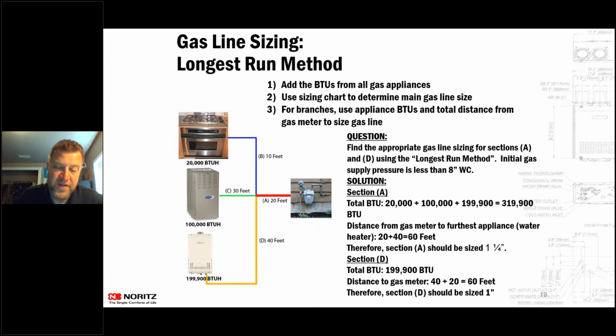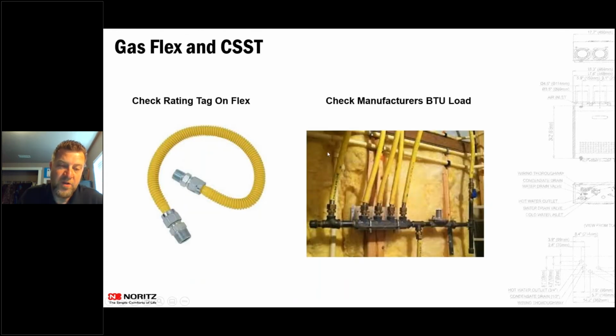or if you're not using gas flex, if you're hard piping, or if you're using CSST, you would want to go. So when you are flexing from your hard iron pipe or whatever you're using going in there, gas flexes are just fine, but you need to check the rating tag that's on that gas flex to make sure it will deliver enough BTUs for that unit. So there's a lot of gas flexes out there where the end connections are 3/4, but it's still only a 5/8 OD, or it's a 3/8 OD.